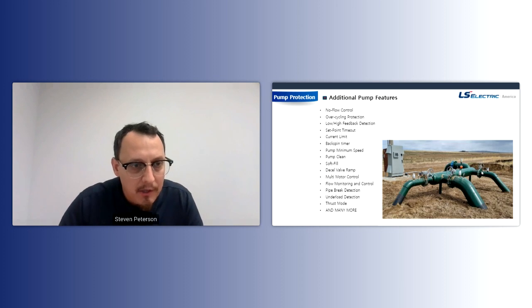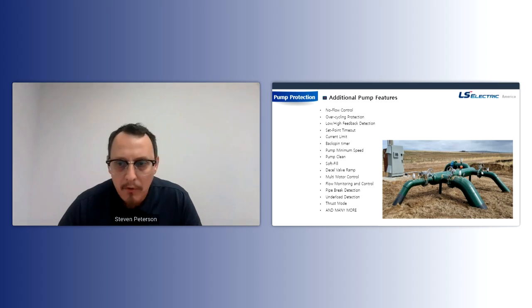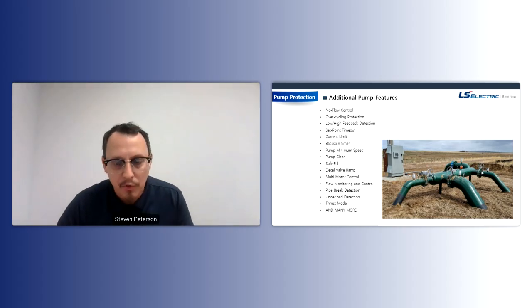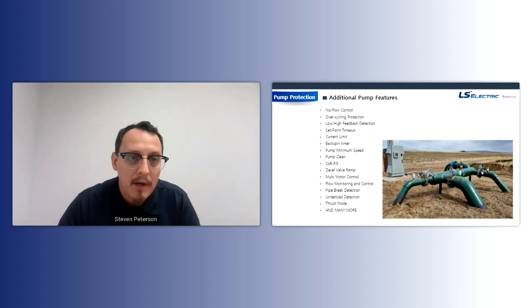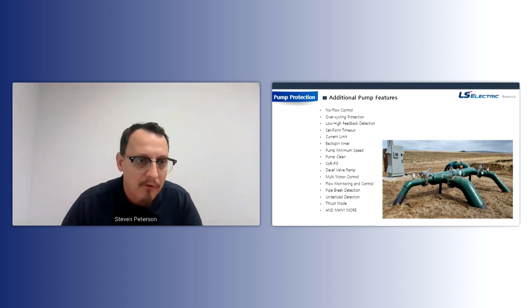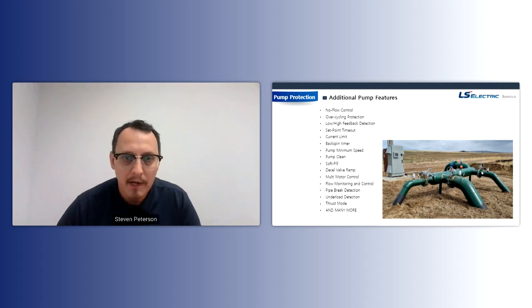That was just a brief introduction on lead lag. It's pretty easy, especially as long as you use the macro. The only hardware you need is 2 wires to go from one drive to another, and that's the Modbus communication. And as long as you're set up with the macro, the drives are going to automatically communicate with each other and tell each other what they have to do, all based on the master drive.